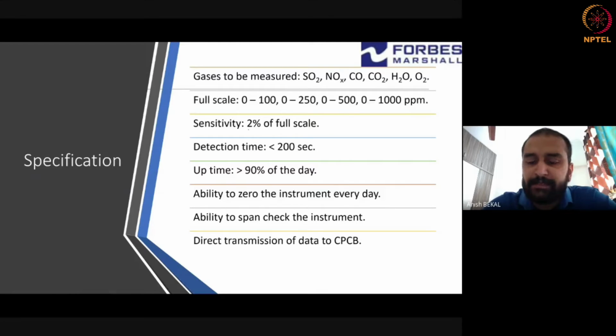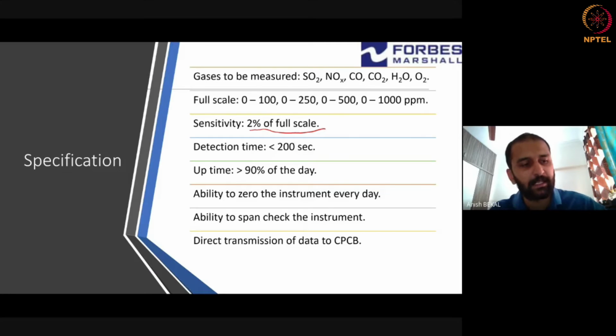Agencies typically say that the sensitivity that you want should be 2% of the full scale. That is very important, because if you have the range 0 to 100 and the minimum resolution that we offer is only 10 ppm, that is not a very good sensor, because you get only 10 points between 0 to 100. What government agencies basically ask for is something which is 2% of the full scale. So I should be able to measure 2 ppm sensitivity for this, 5 ppm for this, and equivalently for 1000 ppm, you're talking about 20 ppm kind of sensitivities. So when you say I have a range for this sensor, you should make sure that sensitivity is less than 2% of full scale.